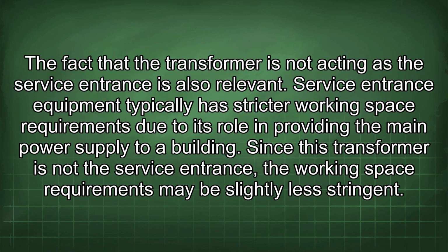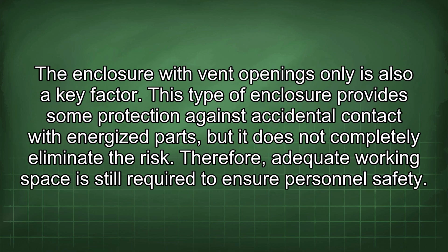The fact that the transformer is not acting as the service entrance is also relevant. Service entrance equipment typically has stricter working space requirements due to its role in providing the main power supply to a building. Since this transformer is not the service entrance, the working space requirements may be slightly less stringent. The enclosure with vent openings only is also a key factor. This type of enclosure provides some protection against accidental contact with energized parts, but it does not completely eliminate the risk. Therefore, adequate working space is still required to ensure personnel safety.